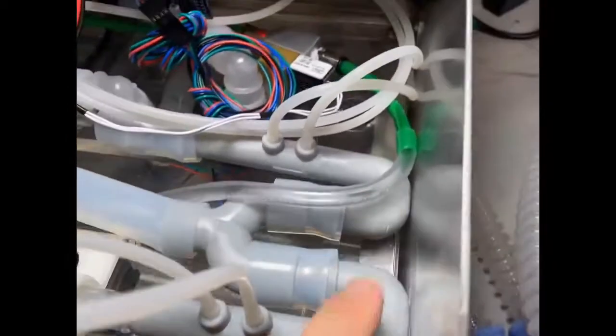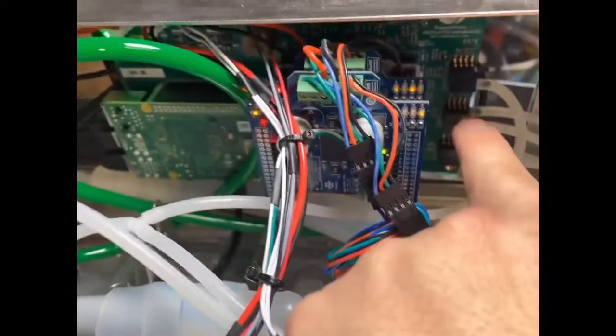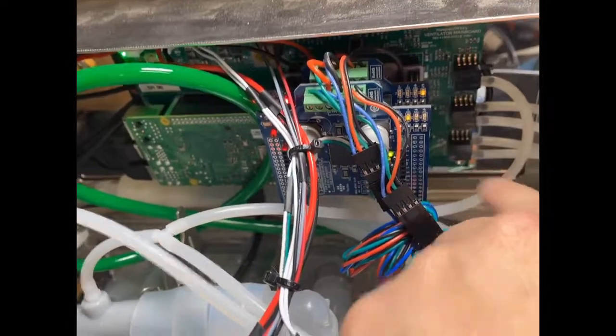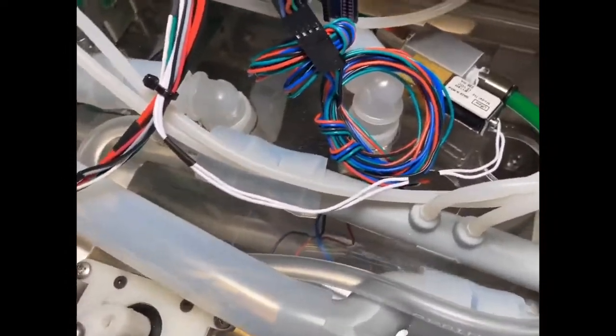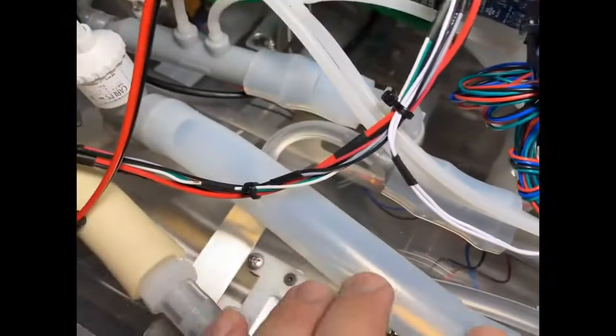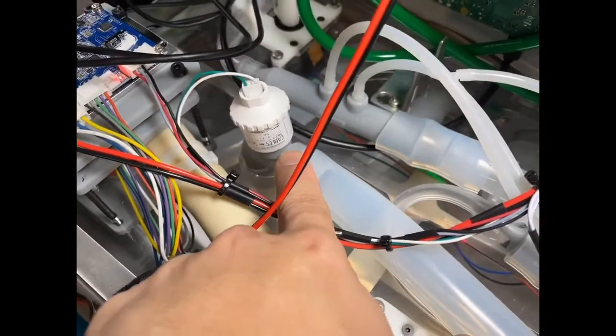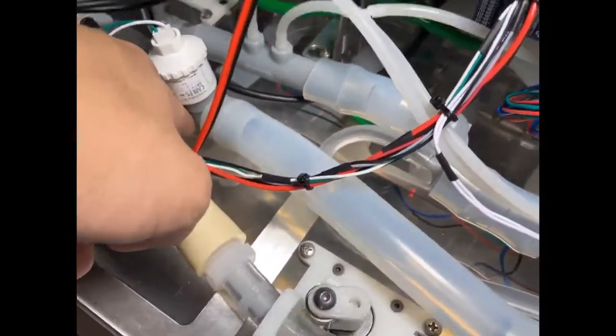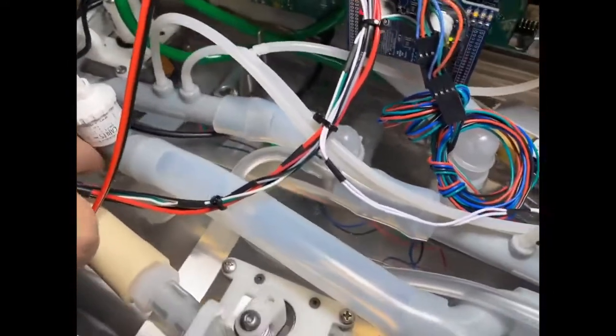That gets translated into a differential pressure, which goes into our custom designed circuit board, where it is measured as flow. So we continue along this path to the outlet path to the delivered oxygen sensor, and this leads out to what is now connected to the quick lung.